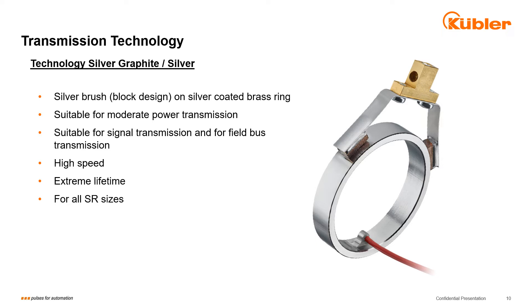I am now coming to the combination of silver against silver. Out of two possibilities, we firstly see a similar arrangement as with silver against brass, with the difference that the brass ring is now plated with a layer of hard silver on its operational surface. In comparison to a pure brass ring, the silver plating enables suitability to transmit signals and fieldbus data up to 100 Mbit per second in contacting mode. Under certain circumstances, even 1 Gigabit per second is possible. The huge customer advantage is that no electronics are necessary to modulate the signal before or after transmission — it goes over the slip ring like over a common stationary network connector, and accordingly the transmission protocol is in no way influenced by the slip ring.